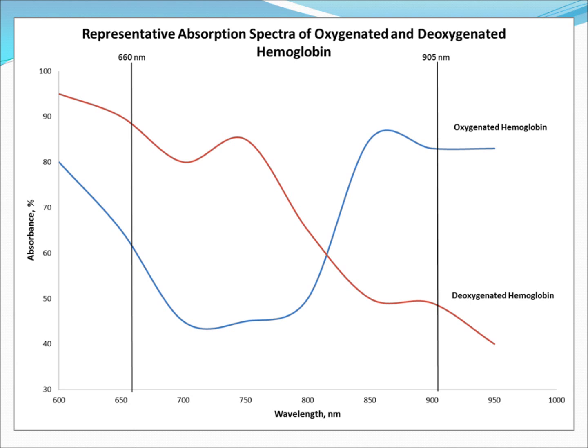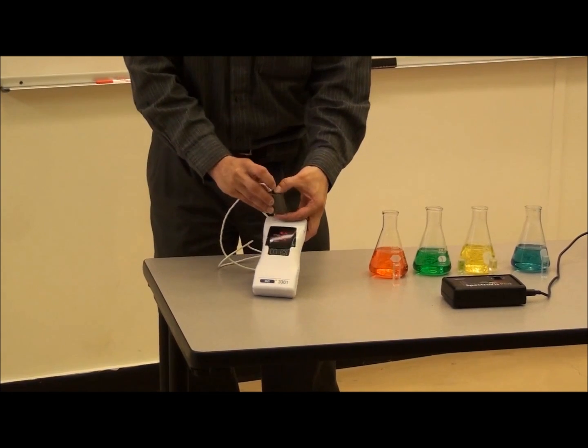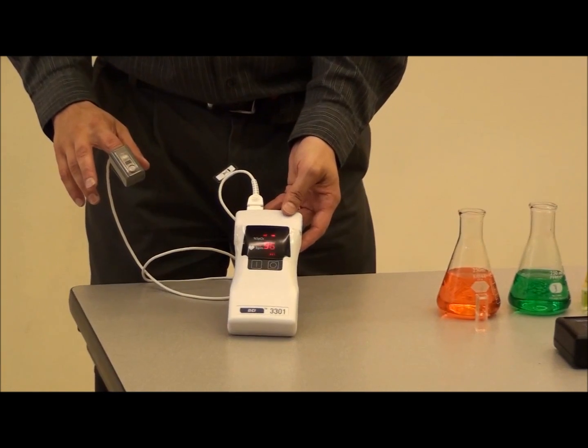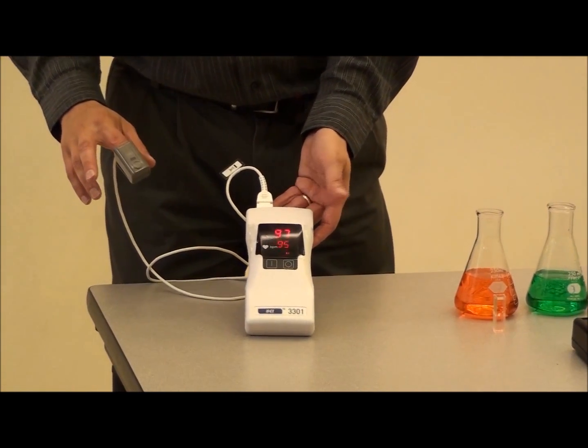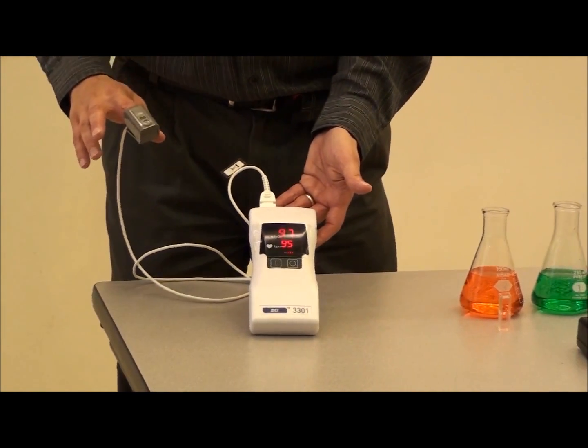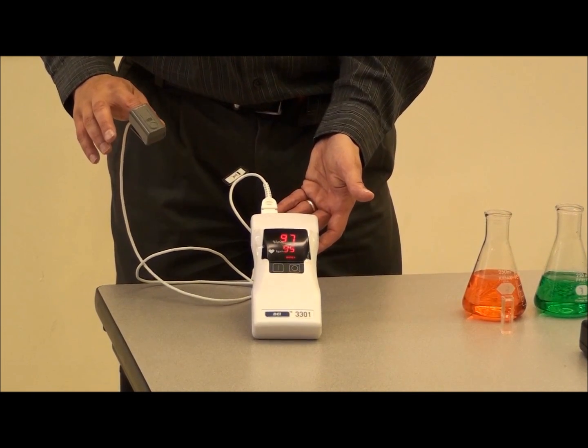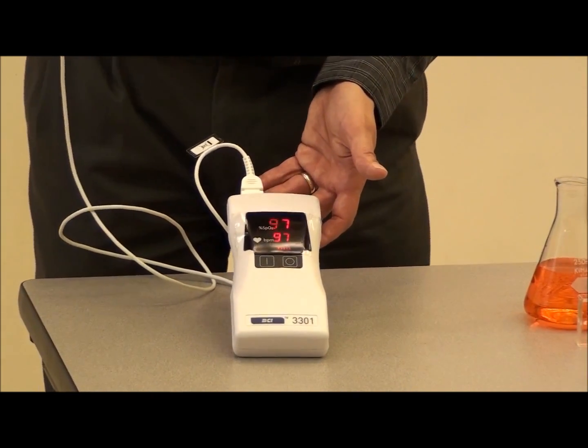The LEDs in the sensor emit photons of radiation, either red light or infrared radiation, that pass through a relatively translucent part of the body. For the case where the instrument has a finger probe, this would be my finger that the radiation passes through. The photons that successfully pass through my finger are subsequently detected by the photon detector. The photodetector thus measures the intensity of the transmitted signals at 660 and 905 nm.